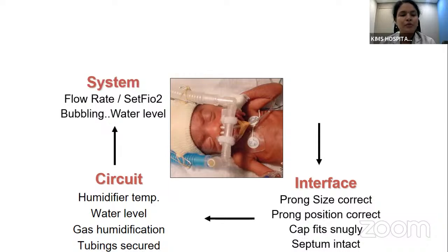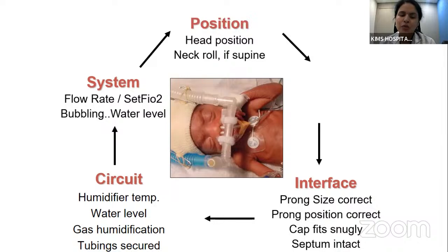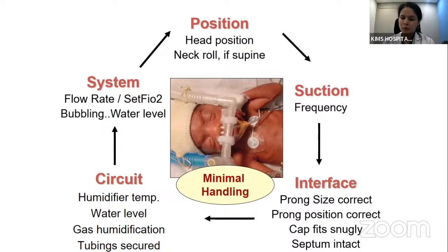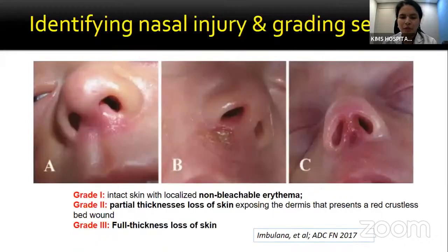When it comes to monitoring of the system, one needs to monitor that the set flow, FiO2, as well as the pressure are appropriate and desirable. It is to be ensured that there is continuous appropriate bubbling, which is neither too vigorous nor too soft. And it is also to be ensured that the baby is appropriately positioned with head in the midline with a neck roll if possible to facilitate mild extension of the neck, and appropriate minimal suction must be performed in order to ensure patency of the nostrils.